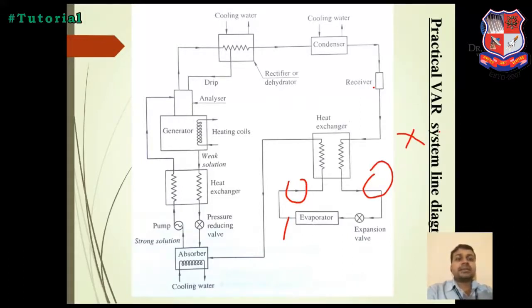You have to use one heat exchanger, with the inlet from the receiver and the outlet from the evaporator. The heat passes from the outlet to the inlet of the expansion valve, so that at the inlet of the evaporator and expansion device, the refrigerant is cooled down compared to what you get from the condenser outlet.